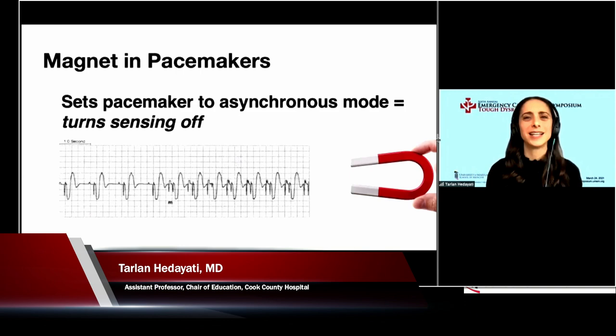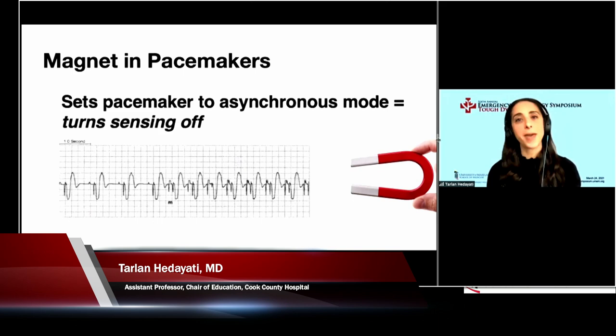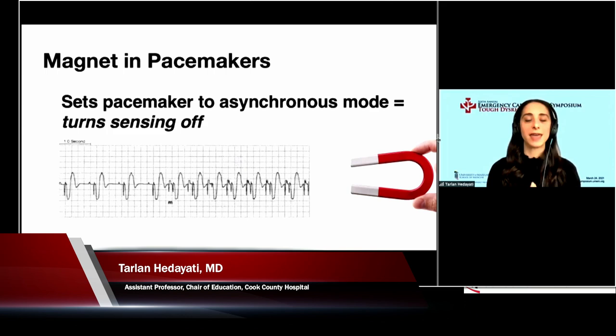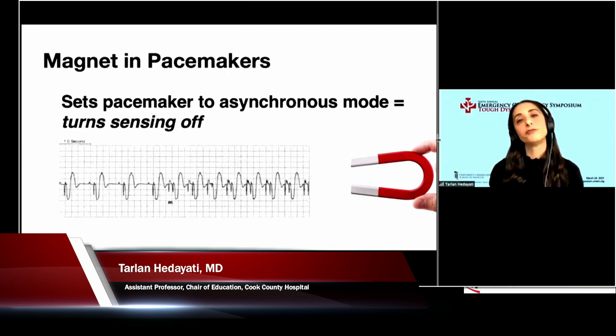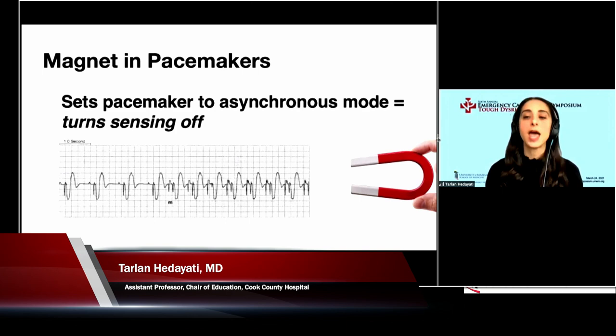What the magnet does is flip a ferromagnetic switch inside the pacemaker or ICD. When you apply the magnet to either of those devices, it flips that switch, setting the pacemaker to asynchronous mode. Asynchronous mode means you are turning the sensing function of the device off.